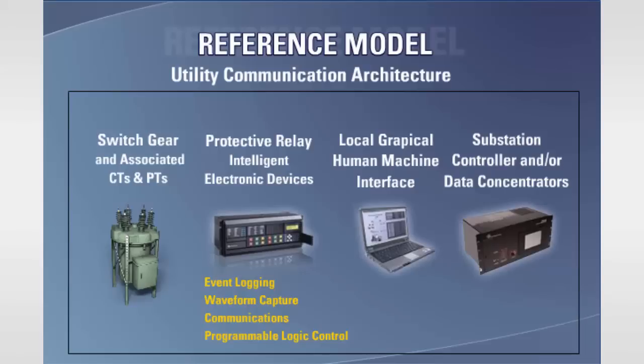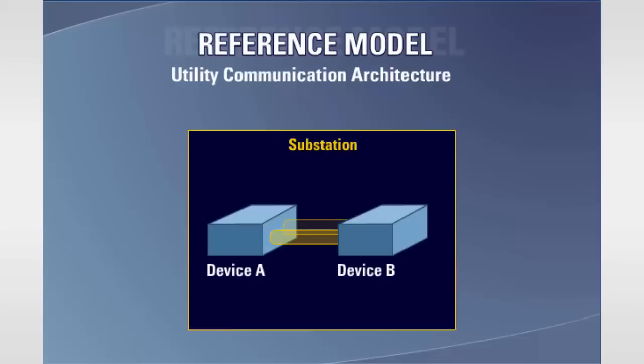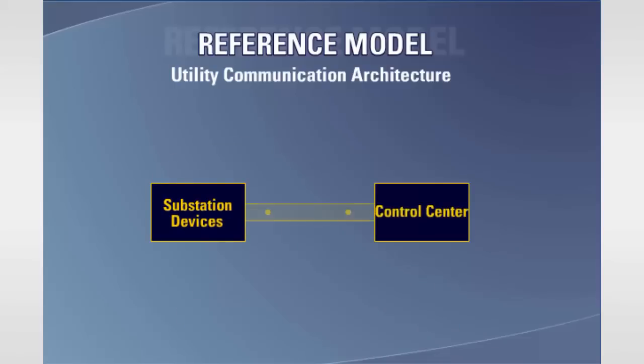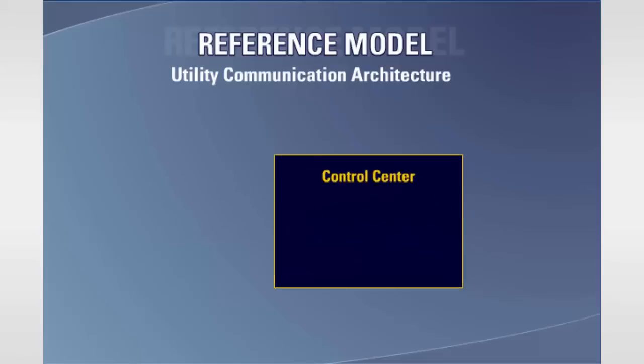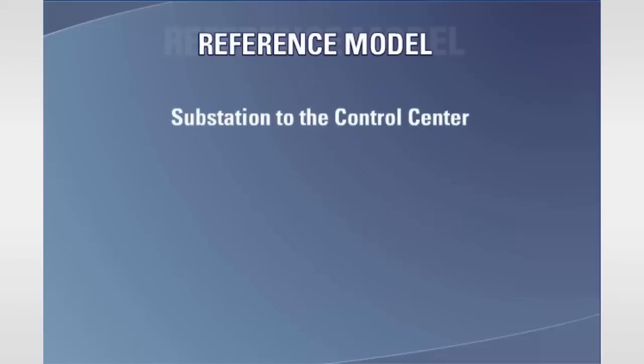Now let's take a closer look at the communications. The communications links vary greatly but fall into three major categories: communication between devices within the substation, communications between devices within the substation and the central control center, and communications between clients at the control center. The IEC 61850 protocol standard divides the communication infrastructure into three areas: the substation to the control center, the station bus, and the process bus.